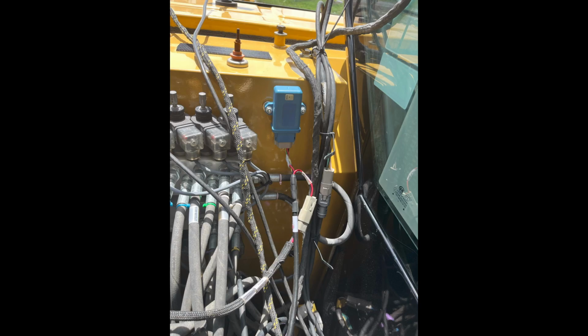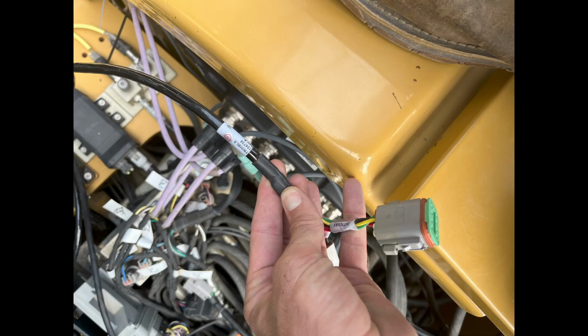The next step is to test the cabling at the Bluetooth to CAN adapter to ensure there is machine power getting delivered to the adapter itself. In the third step, we'll unplug the Bluetooth to CAN adapter from the machine for 30 seconds and then plug it back in. This can realistically be done at the same time as the second step when we unplug the Bluetooth to CAN adapter to check for machine power at the cabling.